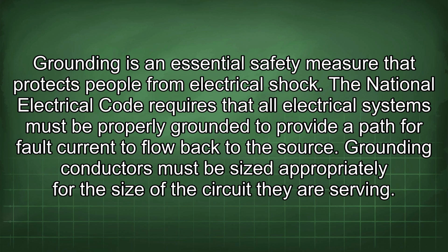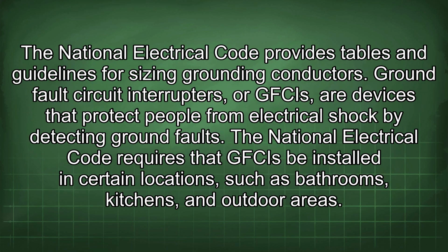Grounding conductors must be sized appropriately for the size of the circuit they are serving. The National Electrical Code provides tables and guidelines for sizing grounding conductors. Ground fault circuit interrupters, or GFCIs, are devices that protect people from electrical shock by detecting ground faults. The National Electrical Code requires that GFCIs be installed in certain locations such as bathrooms, kitchens, and outdoor areas.